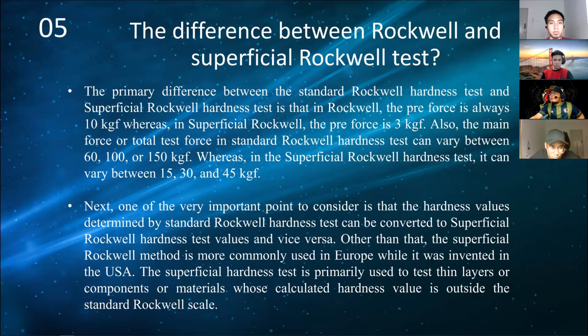Next, the difference between Rockwell and superficial Rockwell test. The primary difference between the standard Rockwell hardness test and superficial Rockwell hardness test is that with Rockwell, the preforce is always 10 kgf, whereas in superficial Rockwell, the preforce is 3 kgf.